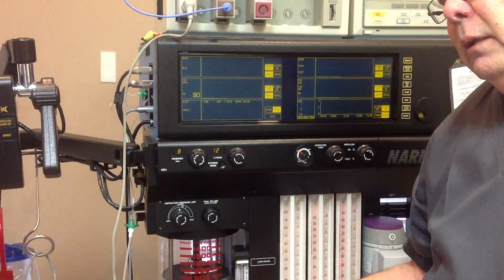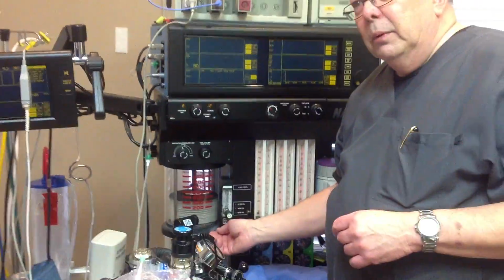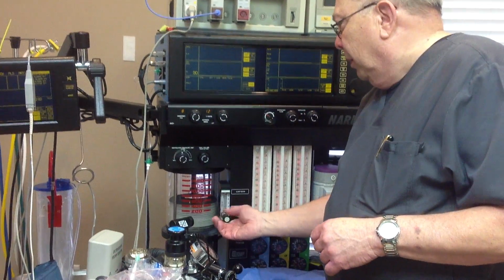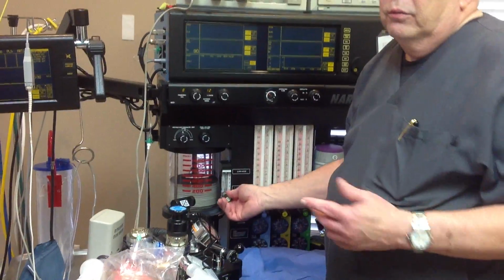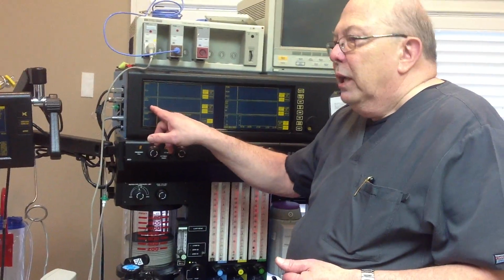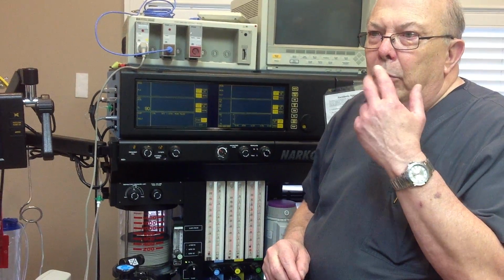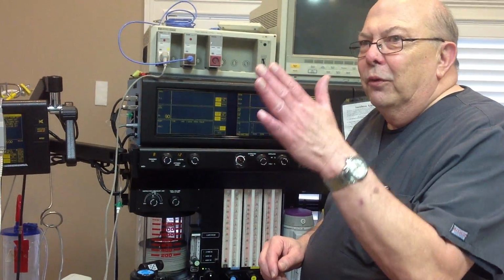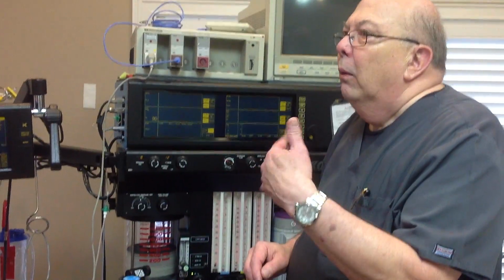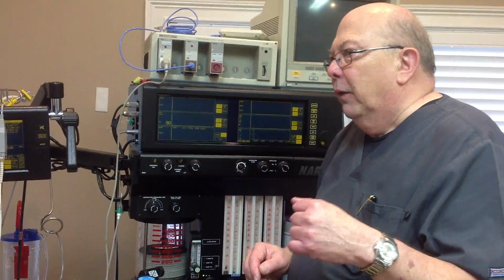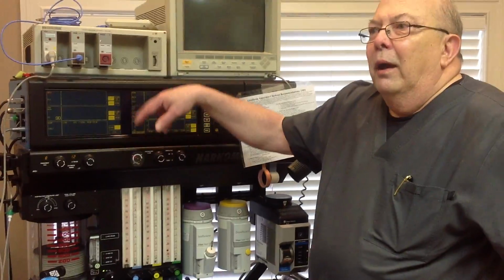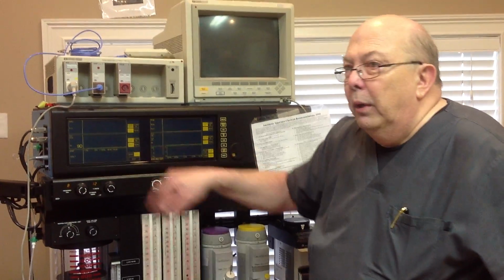Now, if you're doing a MAC and you have nasal prongs hooked up, you will hook it into here, and this will be a separate location, so you would turn that on to the 3 liters for that. Now, it may still be reading 90 over here, but that's not what you're delivering. Remember with nasal prongs, you go 4% over 21 for each liter that you use. So if I'm at 3 liters, I'm probably at 32% FiO2 if it's a good fit. And at the same time, with your nasal prongs, you're going to have an attachment that will go to your sampling line and measure your end-tidal CO2. So while your patient's being sedated, you will see that's how they're breathing. If that suddenly goes away, they stop breathing.